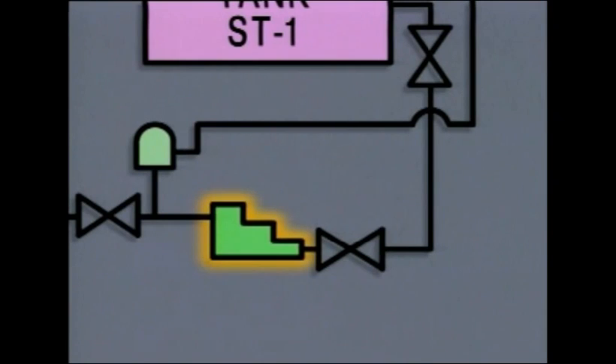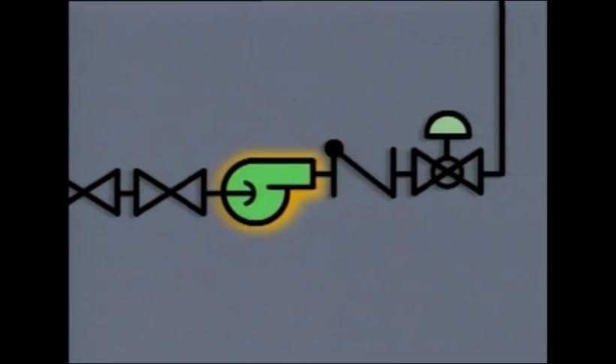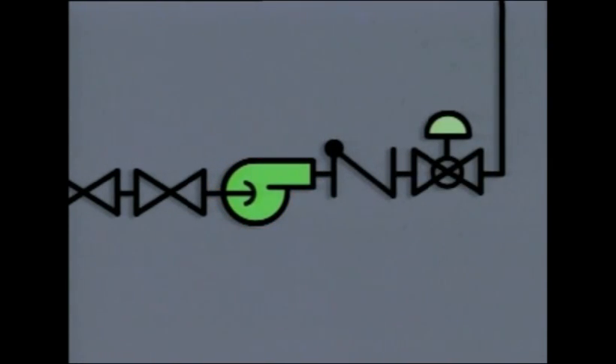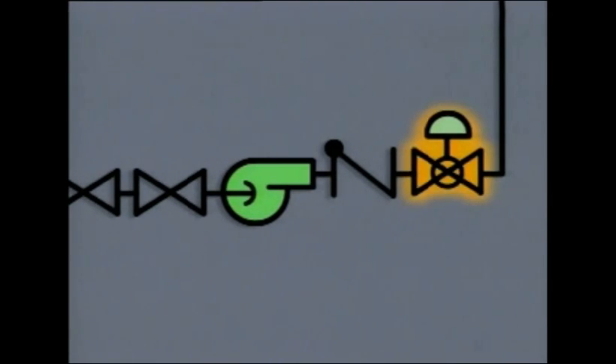This stair step symbol is used to represent a positive displacement pump. Positive displacement pumps are designed to move a specific amount of liquid on each stroke. The other pump symbol on this diagram represents a centrifugal pump. Centrifugal pumps move liquid by applying centrifugal force to the liquid. The flow rate through this centrifugal pump is controlled by a valve in the piping on the discharge side of the pump — in this case, a globe valve with a pneumatic actuator.